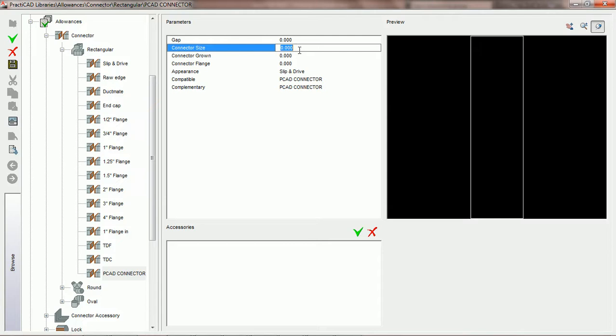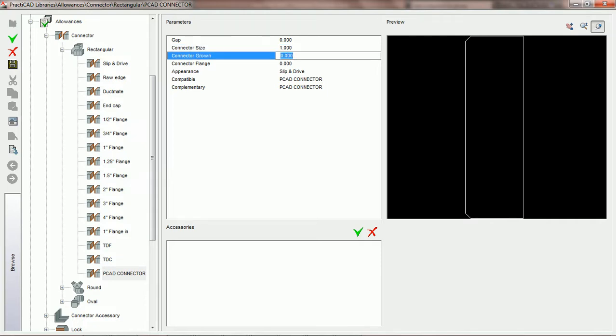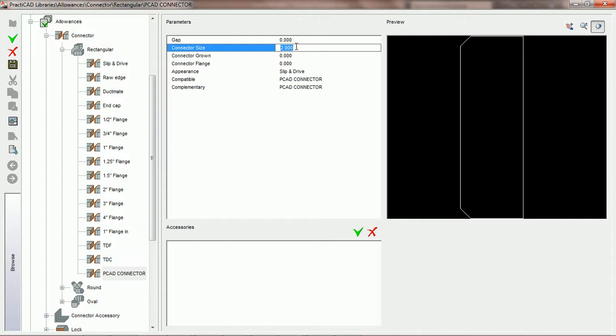The next two parameters we have are the parameters for connector size and connector grown. Connector size parameter is simply the length of the allowance itself. If we set it to 1 inch, you can actually see in the preview that PractiCAD will add a 1-inch allowance. To demonstrate the allowance, we're currently in the appearance slip and drive. If we were to set the connector size to 2, that would mean that the connector size would be 2 inches. Now the connector size parameter is actually being imported from PractiCAM if you imported it. However, you can design any connector you want here.